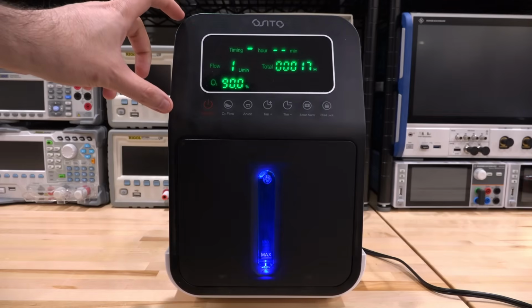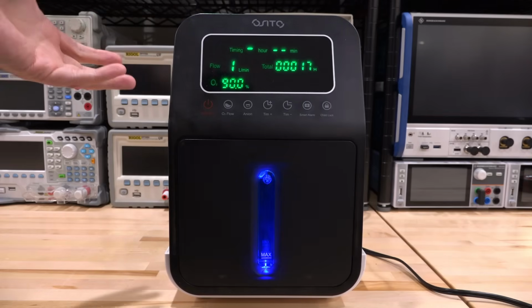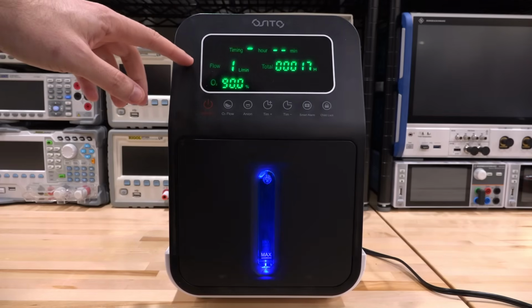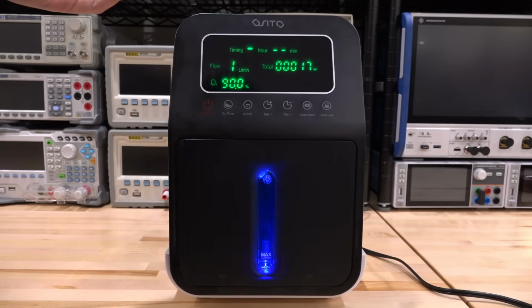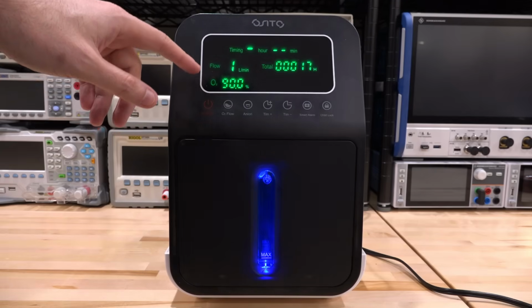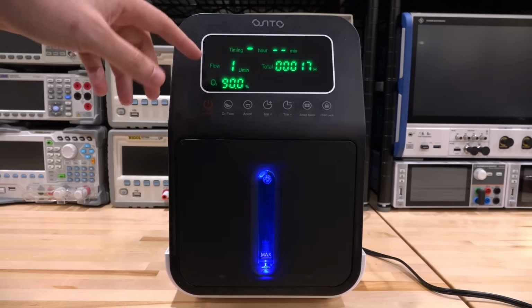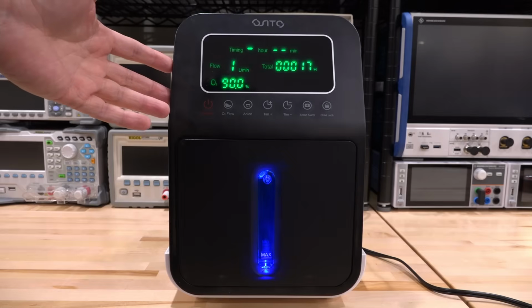Now the controls of a unit like this are really simple because they're meant to be used by any average user. You have the flow in liters per minute, the number of hours this thing has been running, and the O2 concentration. Although I have huge doubts about this number, we'll talk about it when we actually take a look inside of it.